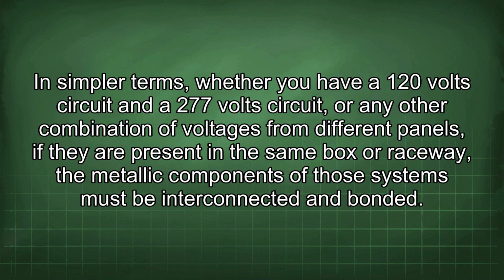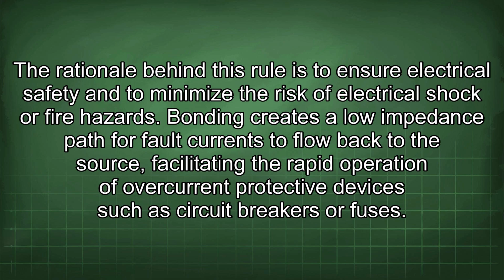In simpler terms, whether you have a 120-volt circuit and a 277-volt circuit or any other combination of voltages from different panels, if they are present in the same box or raceway, the metallic components of those systems must be interconnected and bonded. The rationale behind this rule is to ensure electrical safety and to minimize the risk of electrical shock or fire hazards. Bonding creates a low impedance path for fault currents to flow back to the source, facilitating the rapid operation of overcurrent protective devices such as circuit breakers or fuses.